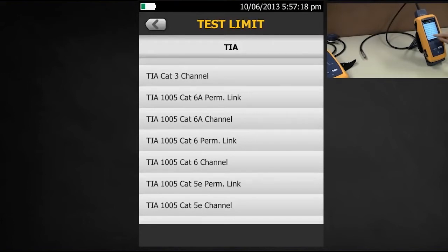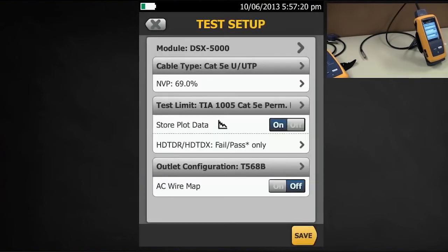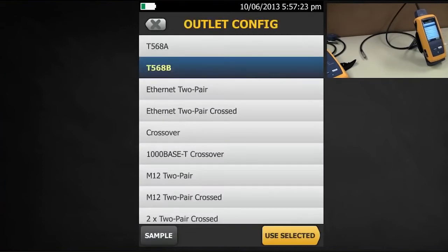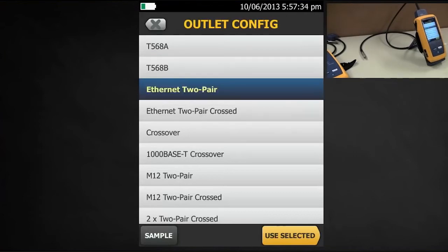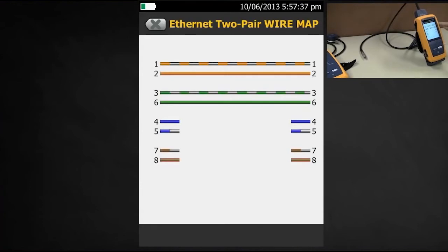So if I tap TIA 1005 CAT5e and then go to my Outlet Configuration — not only do I get T568A and T568B, I now get these other options here as well. If I tap Ethernet two pair and then tap Sample, there we go — I'm only going to be testing two pairs on this occasion.